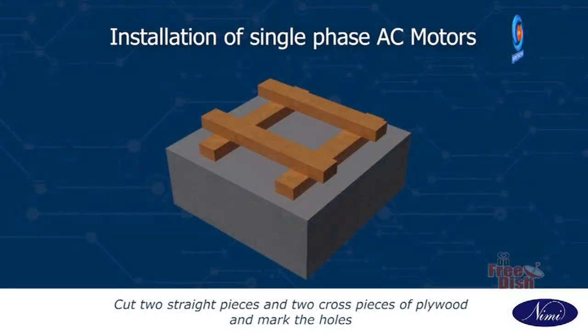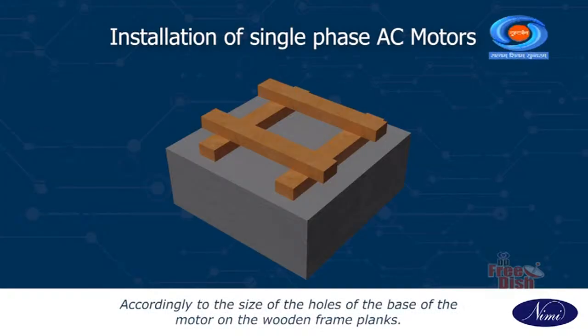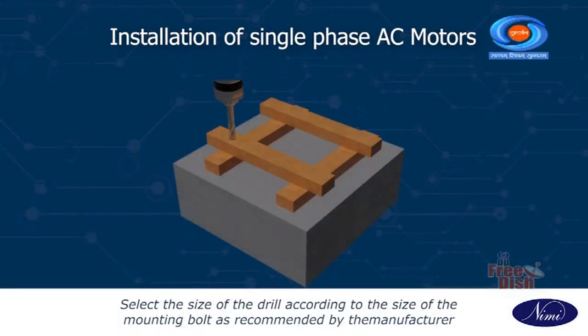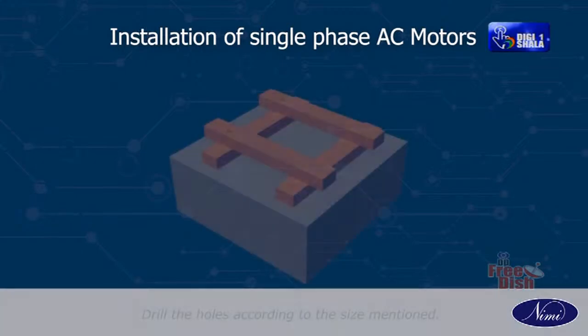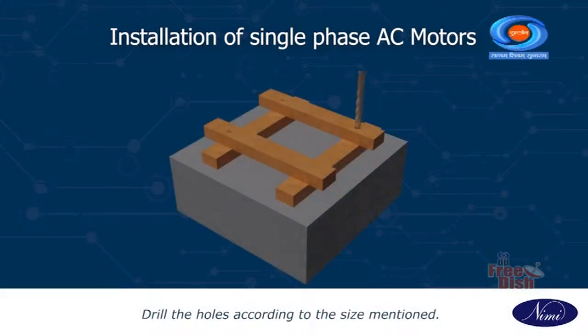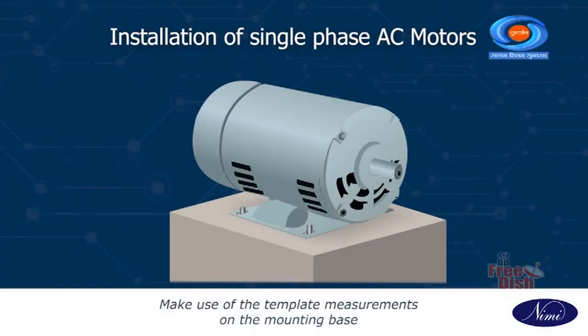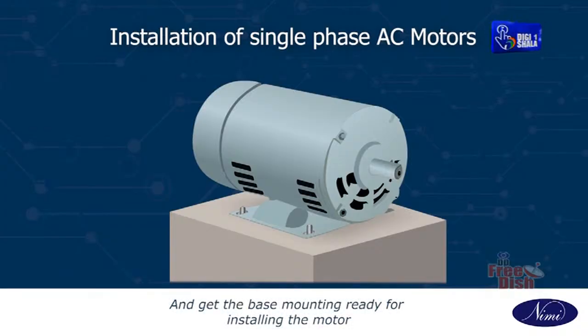Cut 2 straight pieces and 2 cross pieces of plywood and mark the holes according to the size of the holes of the base of the motor on the wooden frame planks. Select the size of the drill according to the size of the mounting bolt as recommended by the manufacturer. Drill the holes according to the size mentioned. Make use of the template measurements on the mounting base and get the base mounting ready for installing the motor.